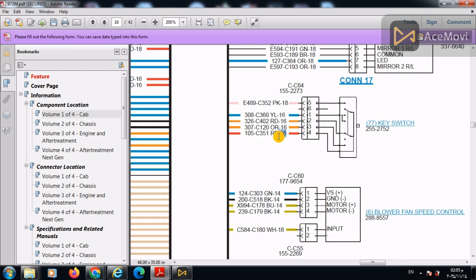16 is the size of the wire. It is American wire gauge and it is opposite to the millimeters. So, whenever this number increase, the thickness of the wire decreases opposite to the millimeters. If we find, for example, a wire which is 4 American wire gauge, it indicates that it is very thick wire. For example, 35 millimeters.